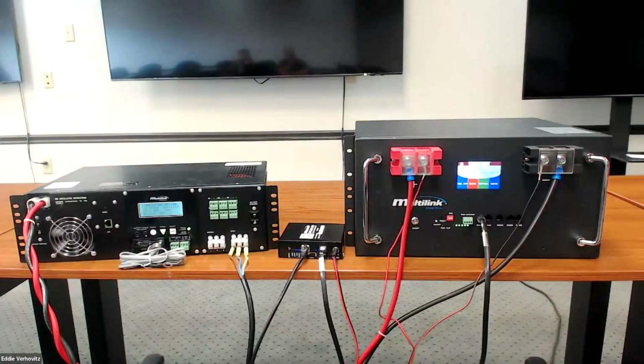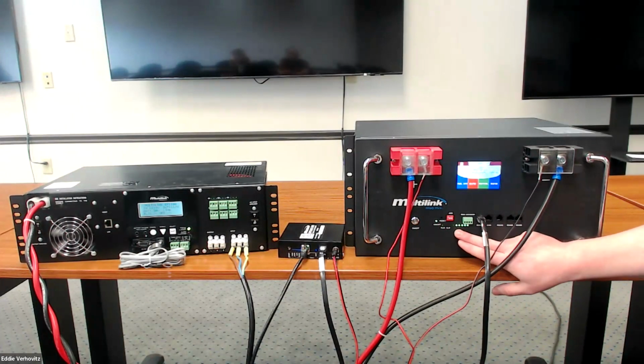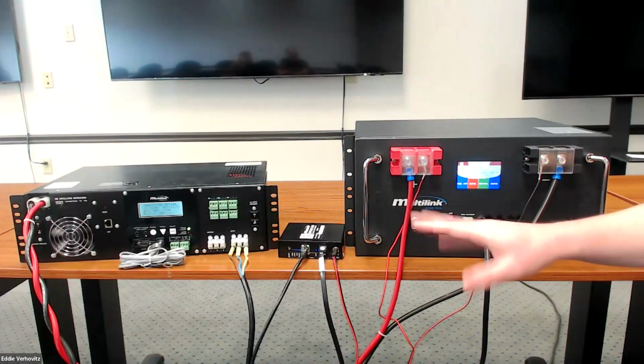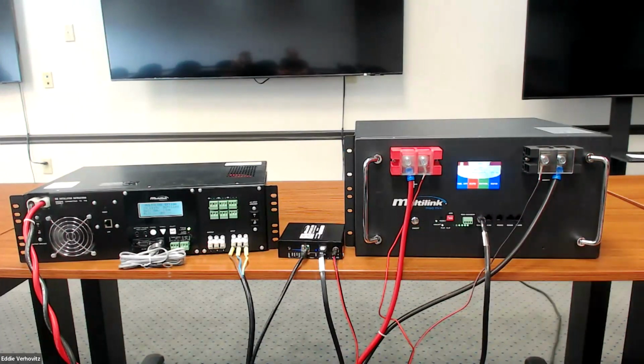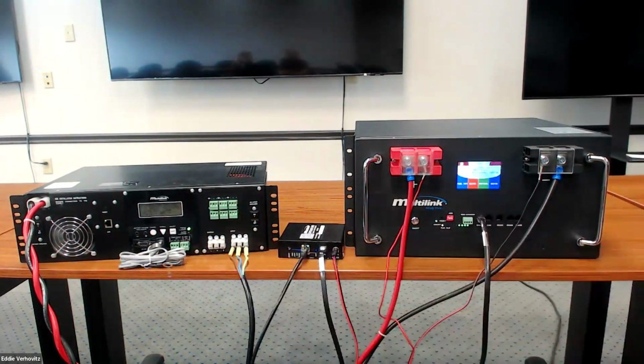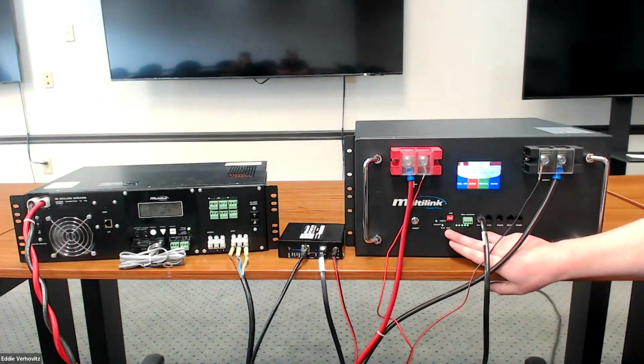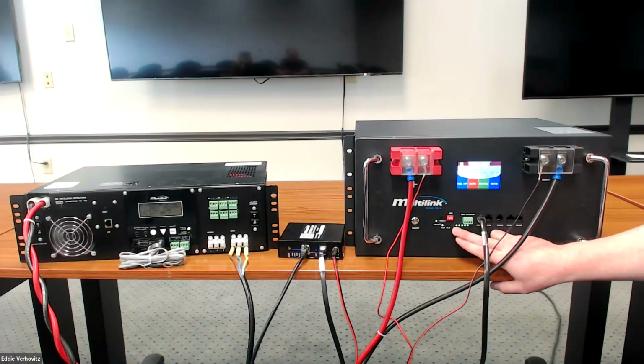Now we'll close the battery breaker on our EP1100. If we look at the LEDs, after a brief moment, maybe 15 to 30 seconds, our charger will start. During that time, our charger has started. We currently don't have any alarms on our EP1100, so we're not seeing any flashing alarm LED conditions. We don't have an alarm condition on our Pantheon battery, but we do have a flashing LED on our state of charge row—the leading LED will flash during charge.